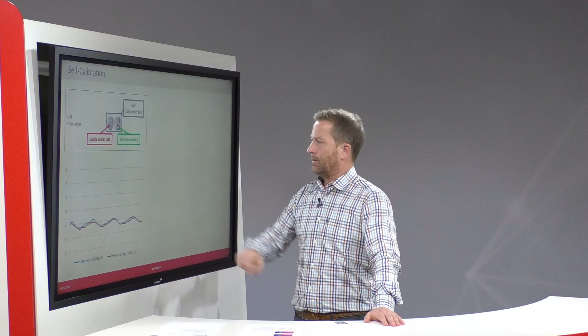The third option is self-calibration. How does that work? First, you order a reference device, which comes together with a calibration box. You run through a wizard, and the software tells you to put the two sensors together, the device under test plus the reference, inside the box, starting the calibration process.